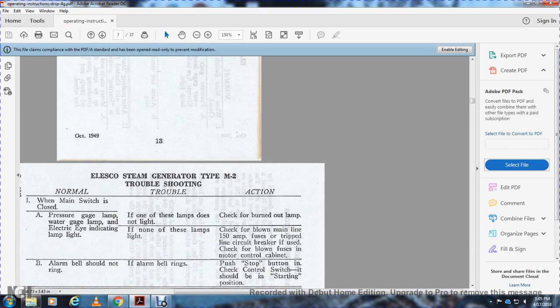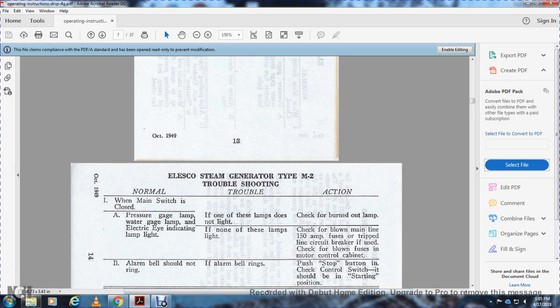Alright, your ELESCO steam generator type M2 troubleshooting. Normal: when the main switch is closed, the pressure gauge lamp, the water gauge lamp, and the electrical eye indicating lamp light. The trouble: if one of these lamps does not light, check for a burned out lamp. If none of these lamps light, check for a blown main line 150 amp fuse or a trip of the line circuit breaker. Also check for blown fuses in the motor control cabinet.